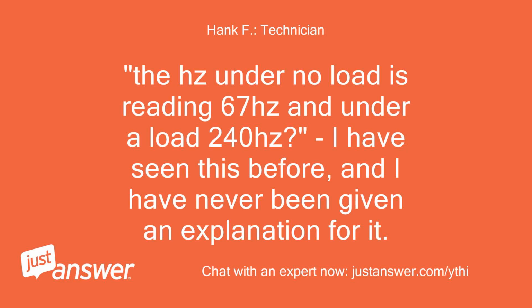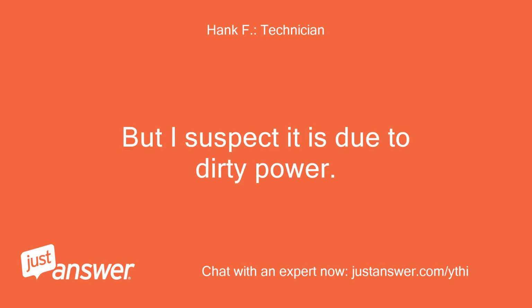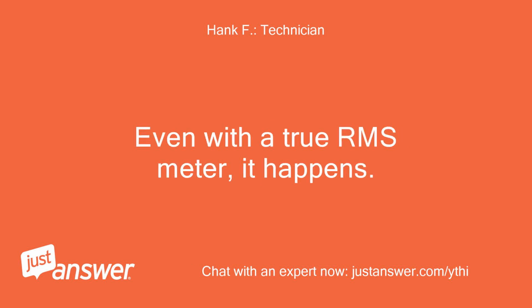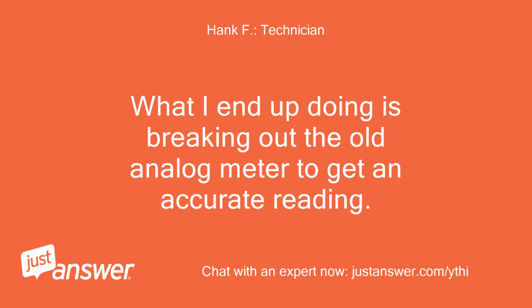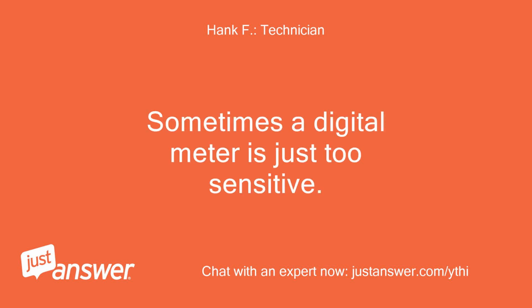The Hz under no load is reading 67 Hz and under a load 240 Hz. I have seen this before, and I have never been given an explanation for it. But I suspect it is due to dirty power. Even with a true RMS meter, it happens. What I end up doing is breaking out the old analog meter to get an accurate reading. Sometimes a digital meter is just too sensitive.